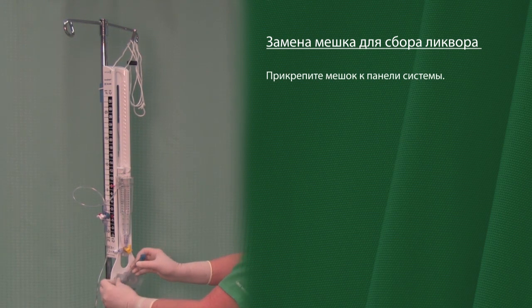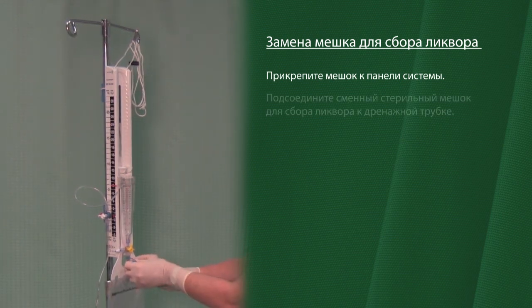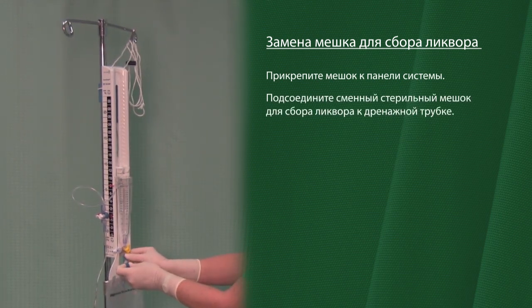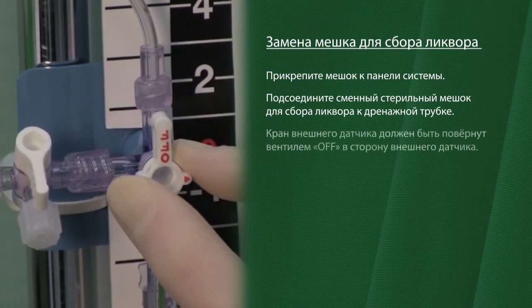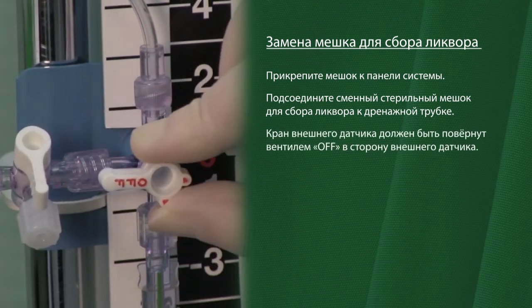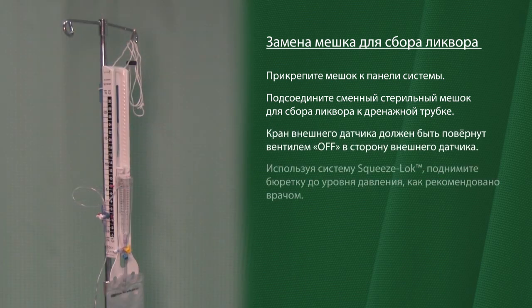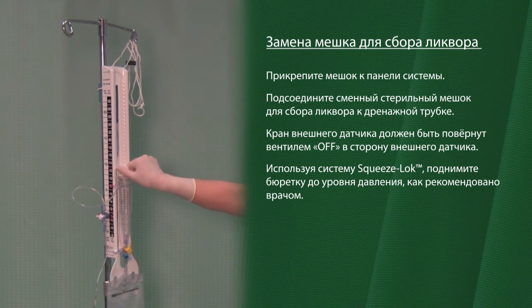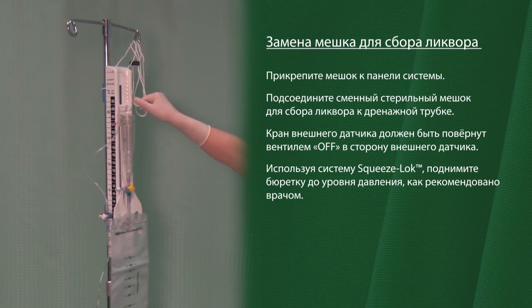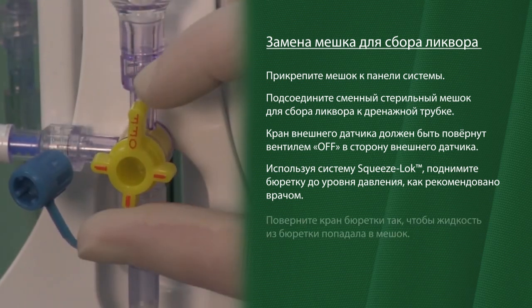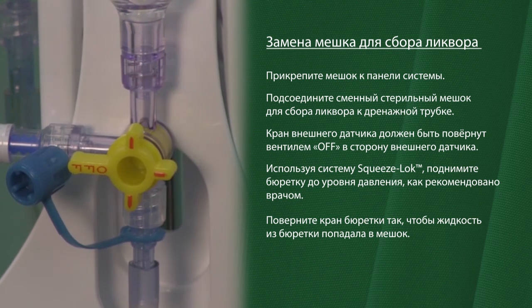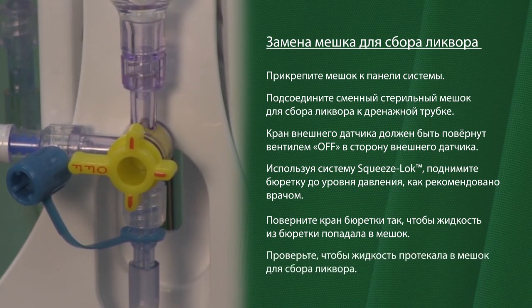Attach the bag to the system panel. Connect the sterile replacement drainage bag to the drain tube. Using the Squeeze-Lok system, raise the burette to the pressure level as ordered by the physician. Reorient the burette stopcocks to allow flow from the burette into the drainage bag. Verify flow into the drainage bag.